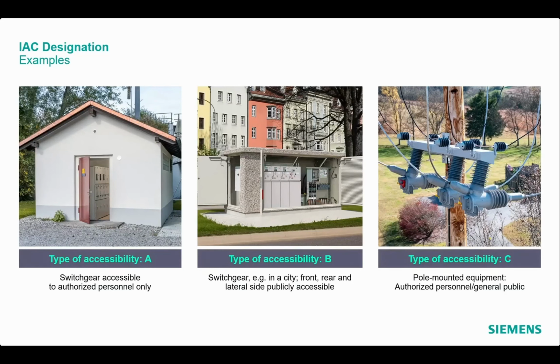The picture in the middle shows a switchgear in a concrete substation in a city where the front, rear, and lateral sides of the station are publicly accessible with the type of accessibility B. The test requirements for type B as per IEC standards are different in comparison to type A. The main goal, however, is to ensure personal safety. The last picture on the right side shows a pole-mounted equipment with type of accessibility C, which could be accessed by both authorized personnel as well as general public while satisfying the corresponding safety requirements for personal safety.